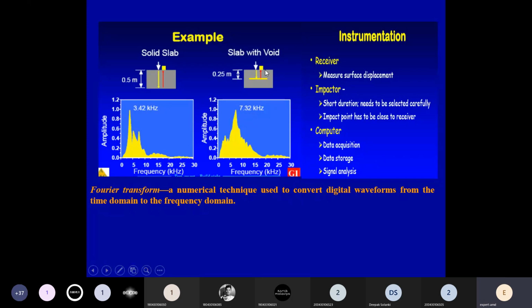If your travel time is less than expected - why expected? Because you know the distance is 0.5 meter in this direction, and when it comes back, it's again 0.5 meter, so the total distance is 1 meter. 1 meter divided by the velocity we found out on a different member of the same grade lets us calculate the expected transit time. If it is less, it indicates either delamination or a problem with the thickness.